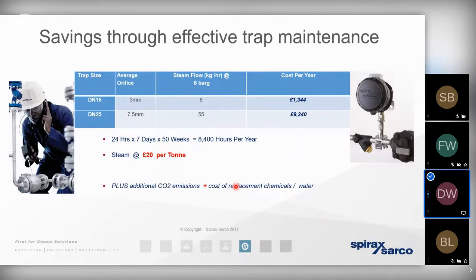So in the case of looking at just one steam trap of a size of 1 inch, 6 bar gauge, that trap could be £300 sterling to replace, but it could be representative of an energy loss that is significantly greater. So if you consider a steam using site that may have 500 steam traps with a failure rate of 1 in 10, you can appreciate why it's strongly recommended that sites would either have a periodic manual audit of the steam trap population, or they'd have some kind of automatic Wi-Fi trap monitoring device for the more important and the greater steam users on that process.